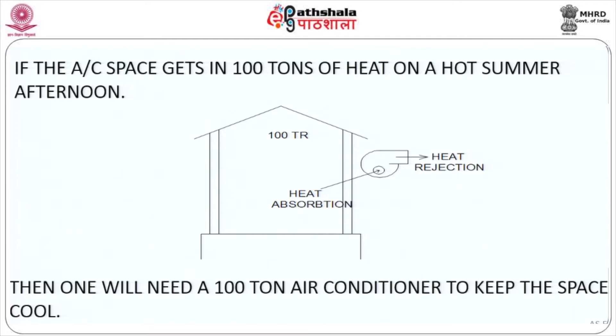Take a simple enclosure. If there is an enclosure which needs, say, 100 tons of air conditioning, 100 tons of air conditioning will need a 100 ton pump. Now, how does one pump out heat? A pump, everybody knows, can be centrifugal or reciprocating, and be familiar that it pulls out the fluid from a receptacle and puts it into another receptacle. Now here, heat is something which is available all over the place, and you've got to remove it from a restricted area, from a room which is to be air conditioned. How do you pump it out?